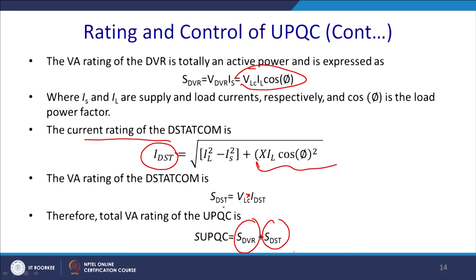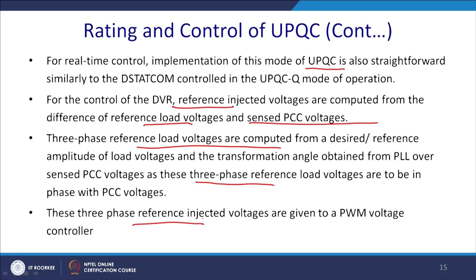So what we can conclude is that the real time control and implementation of this mode, UPQC P, is also straightforward, similar to the D STATCOM control in the UPQC Q mode of operation. For this control, the DVR reference injected voltages are computed from the reference load voltage and the sensed PCC voltage, and it can only correct the sag, mind it. The three phase reference load voltages are computed from the desired or reference amplitude of the load voltage, and the transformation angle is obtained from the PLL over the sensed PCC voltage. This three phase reference injected voltage gives you the PWM required to generate the reference for the voltage source converter. This is the way of operation of UPQC P.